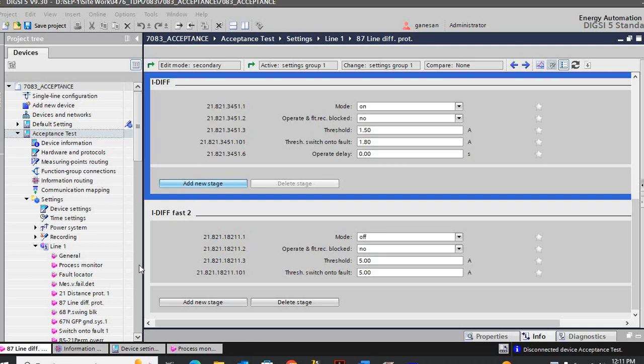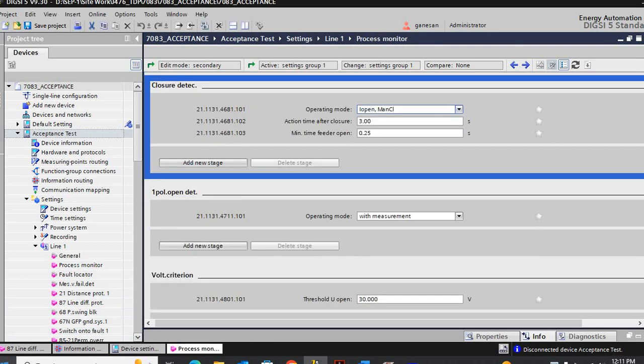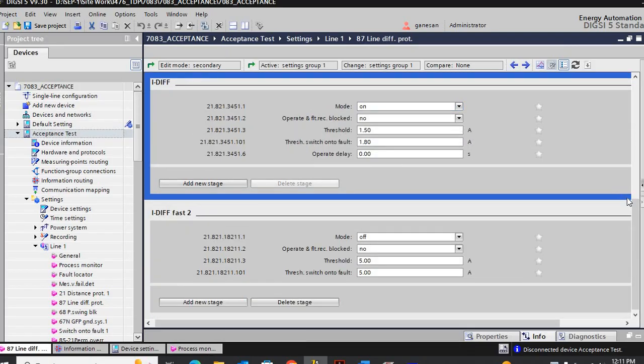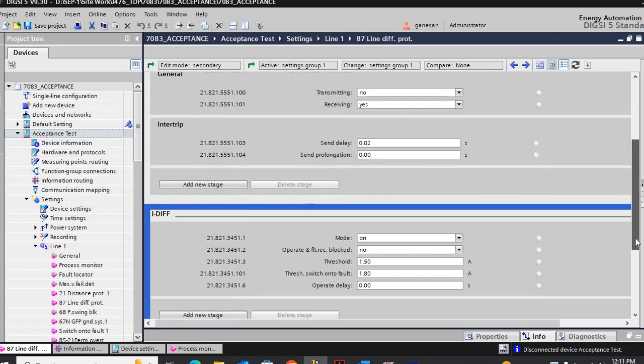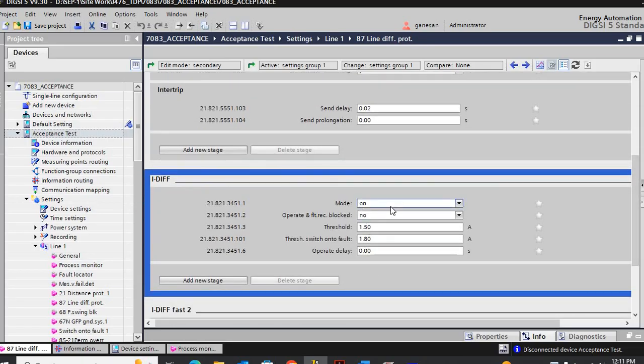Our differential with SOTF — for that function, the differential function must be enabled, and differential must be enabled. The threshold — this is for the differential value — is 1.5, this is the differential pickup. And our switch-on-to-fault condition is 1.8, more than this threshold value, as per the manual.